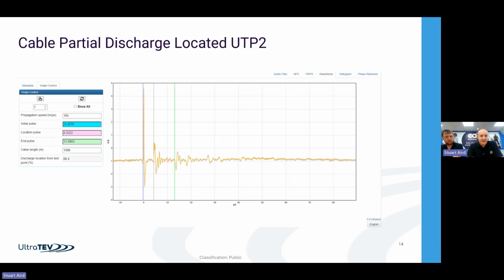I'll just go on to a single screen of that. Now we can see from the data that we've got a cable that's approximately 1,000 meters long. We've got an initial pulse that the device picks up, as we've got an HFCT at the end of the cable. Then as the pulses bounce up and down that cable, we can pick up the second pulse, which gives us an indication of where it is. The time of flight between those two pulses provides the location of the partial discharge. So in this case, we're about 66% of the cable route along the circuit.